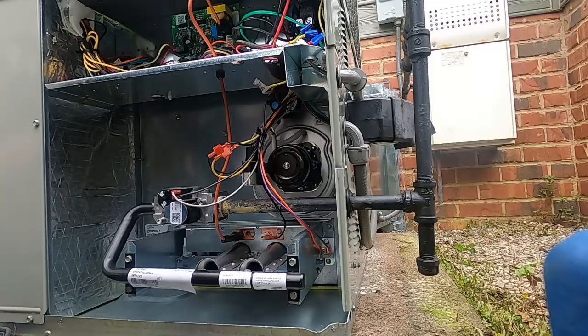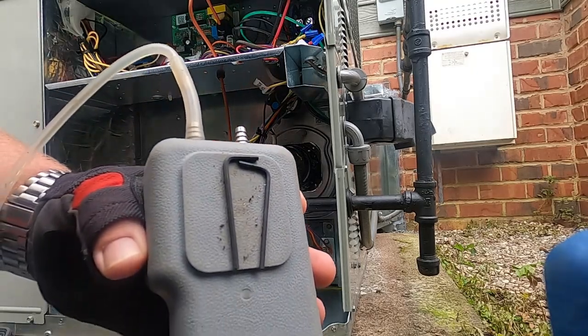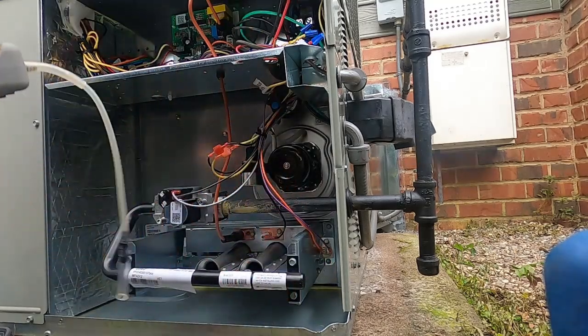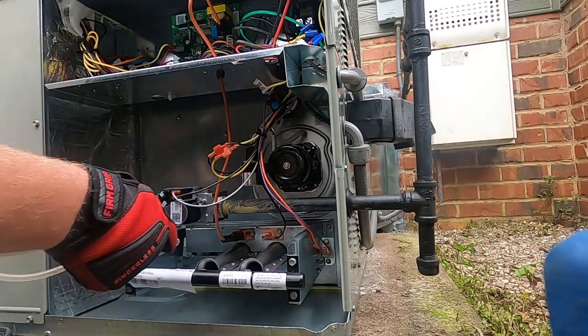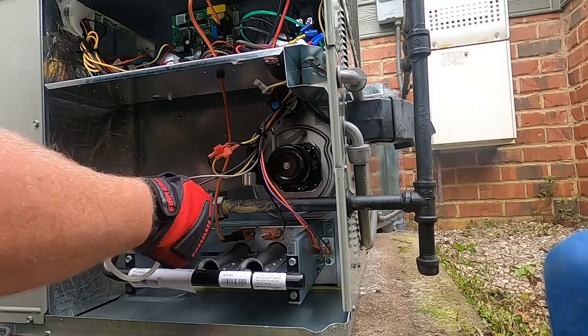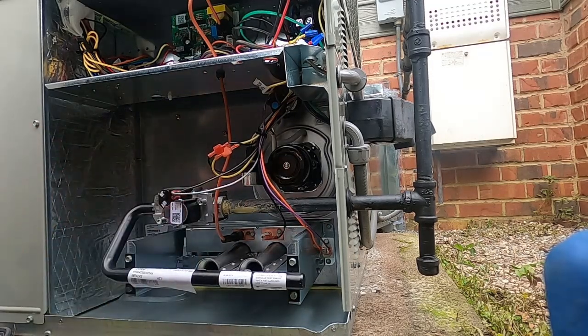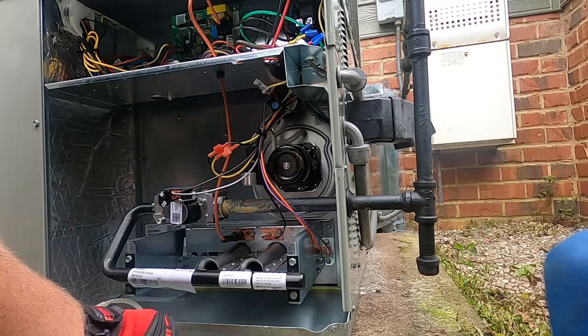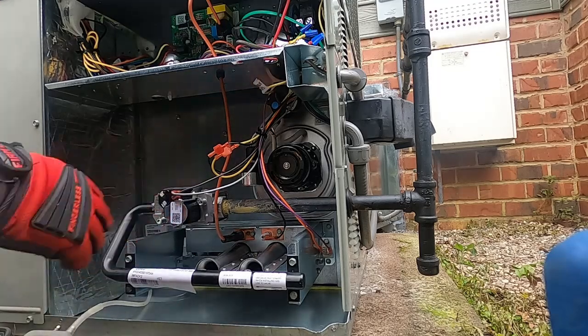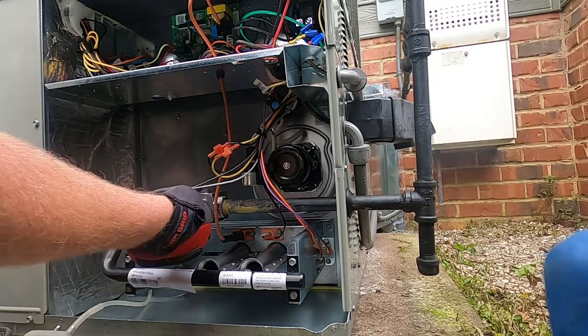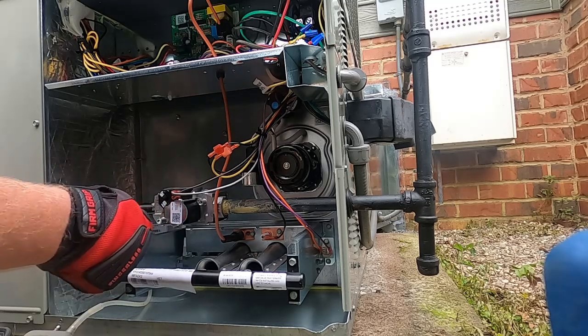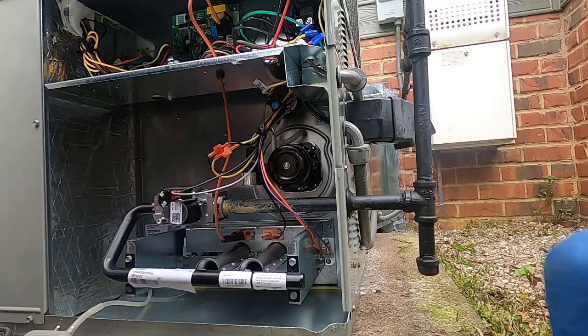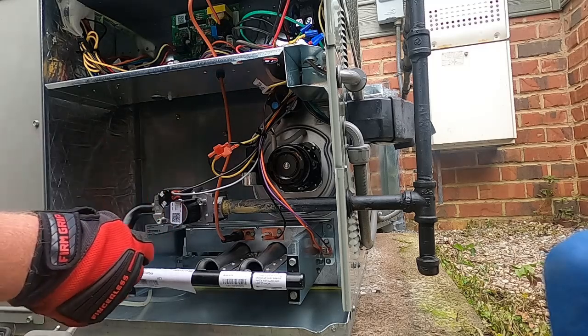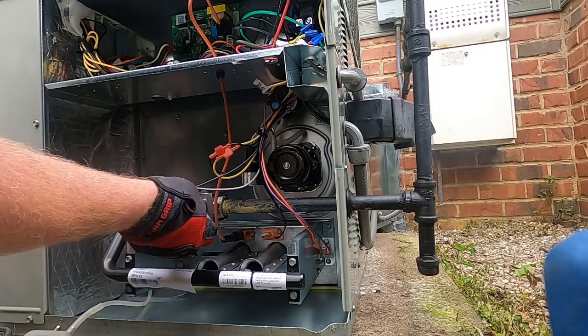But I'm going to check this gas pressure. I keep my little Allen keys stuck on the magnet on the back of my manometer. I use a digital manometer to check the gas pressure on those things. I do have the Field Piece Job Link set, the static pressure transducers, the wireless Bluetooth ones, all that. But they don't react when you're trying to check gas pressure. You're making your adjustments, and by the time it picks it up and gets it to your phone, it's like 4, 5, 6 seconds sometimes. There's just a big delay in that.